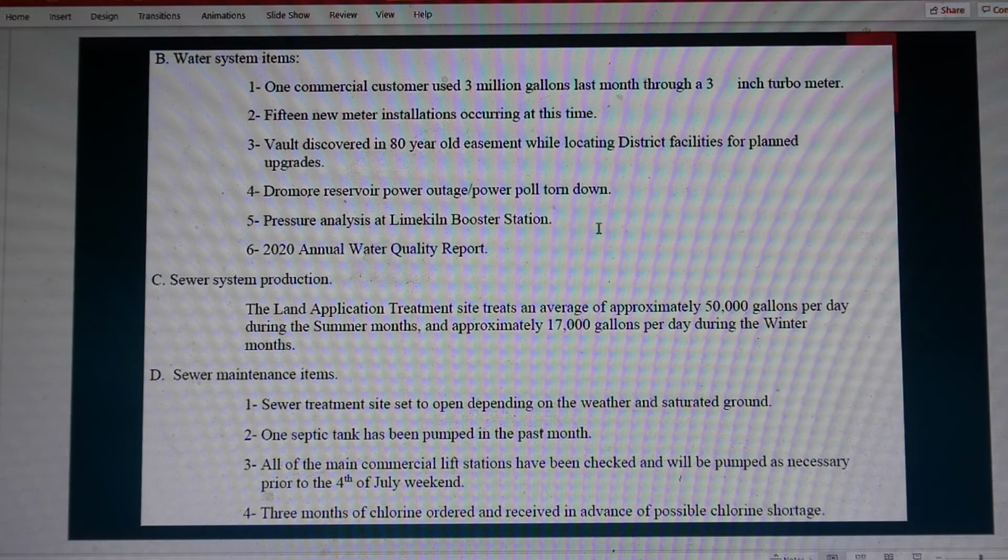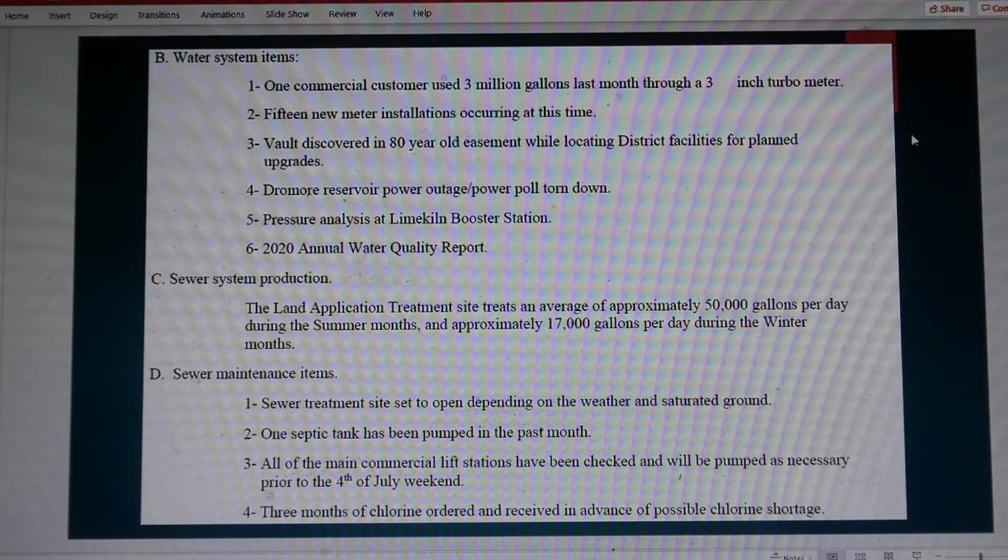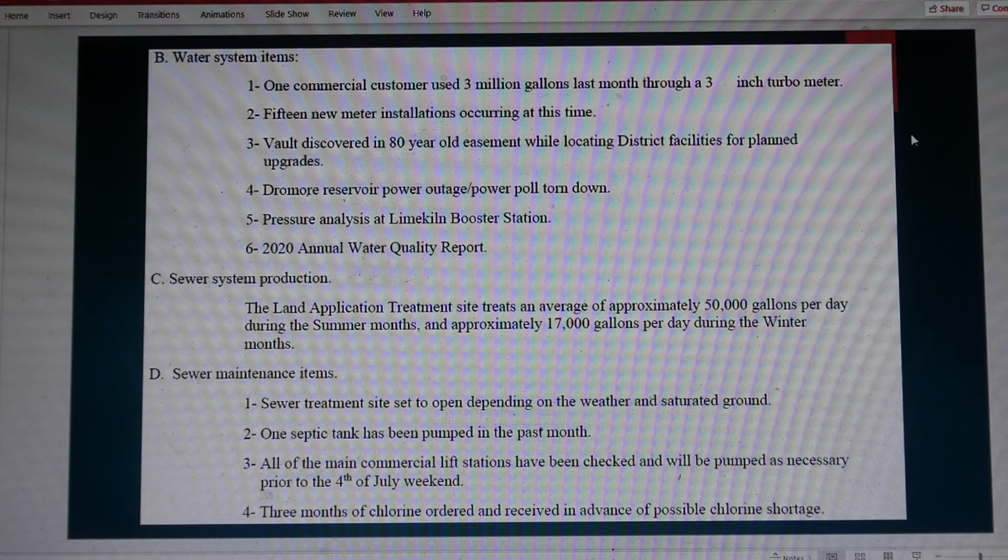Okay, so with that being said, there's always risk in not having properly located utilities when you're in the design phase. Let's say you're putting a water line in and then you find out there's fiber optic or something that's 2 feet off of it and we never planned for it. So our job as engineers is to try to get as many of those facts lined out on the plan so that, one, they're accounted for in the bid, and two, they're planned for in the design. Now, one of the things we're running into, like Bob already indicated, is we don't have a lot of the utilities located out there. But the good news is we know the sewer, because that's going to be a big driver. That's going to dictate our separation requirements from non-potable to potable.